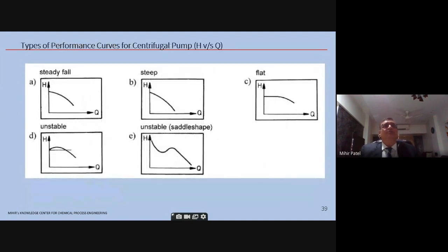Now these are the types of performance curves of centrifugal pumps. As you can see, A is the steady fall, B is the steep curve, and you have the flat curve, C. D and E are unstable curves. For stable performance curves, there exists only one flow rate for each value of head, as is seen in A, B, and C.